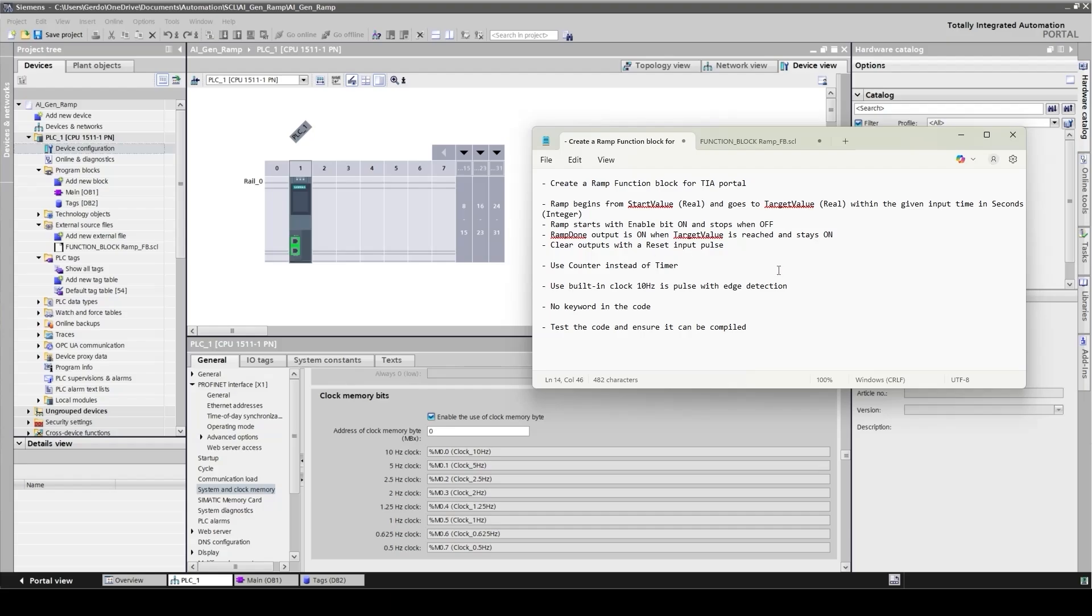In this case, I would like to use counter instead of timer. My personal preference is to avoid using timers inside the function block as much as I can, especially with tools like this. Instead, I can use counter with clock because debugging is much easier. In this case, I'm going to use a CPU built-in clock pulse with edge detection. And as you can see, I've already activated this in the CPU setting. This memory address will give me a 10 hertz clock.